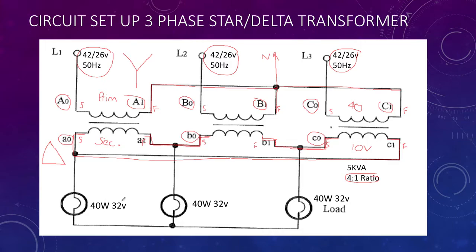Then finally, we have our load. You can see here, our load is three lamps. One side of each of those lamps has been connected together. Therefore, the lamps themselves as a load are connected in star. So we have star, delta, star in this particular case. We're going to be measuring the voltages across our lamps and the voltage coming in on the primary, the volts primary and the volts secondary.